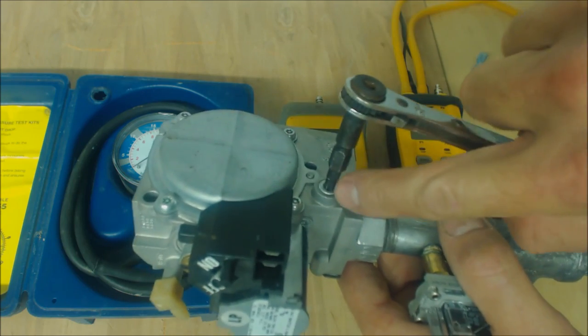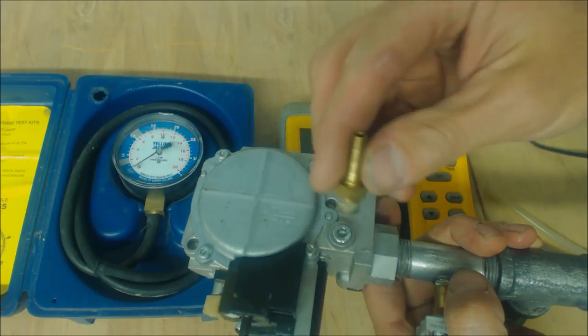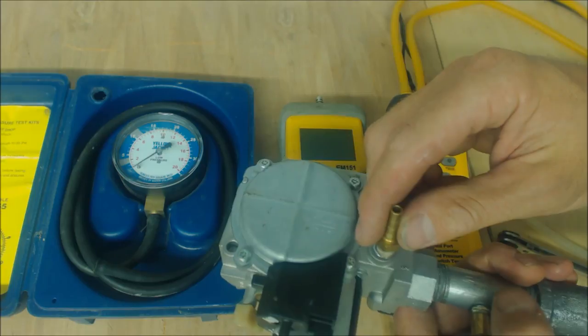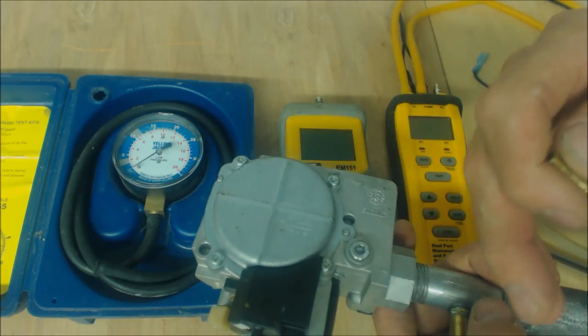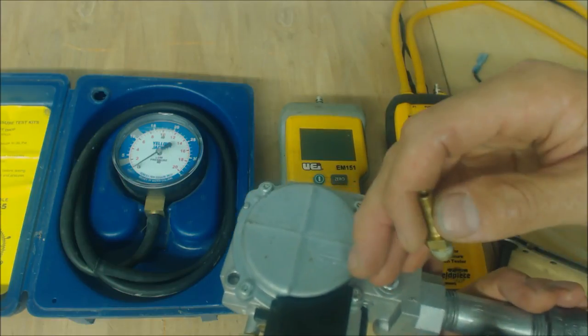For a gas valve, we can check the inlet pressure with this screw that we undo with a service wrench. We turn the gas off, turn the furnace off, take that out, put our brass fitting in, and hook up our manometer to check the pressure. Then we turn the gas valve back on, turn the furnace on, and check our inlet gas pressure.